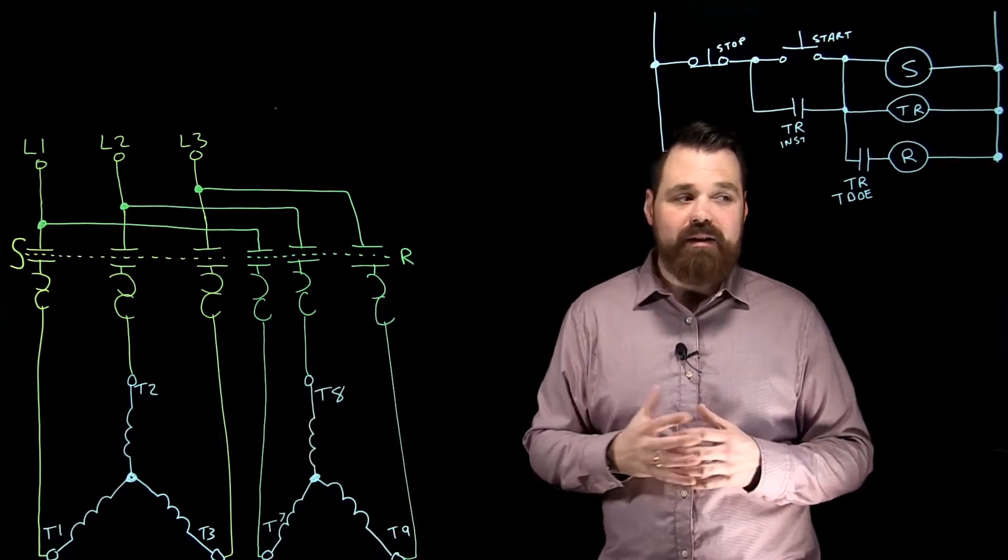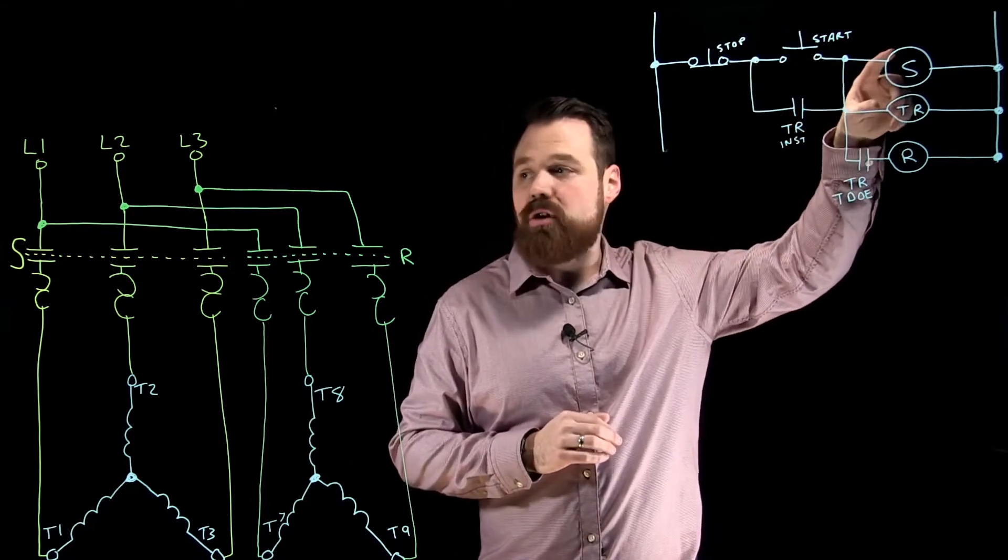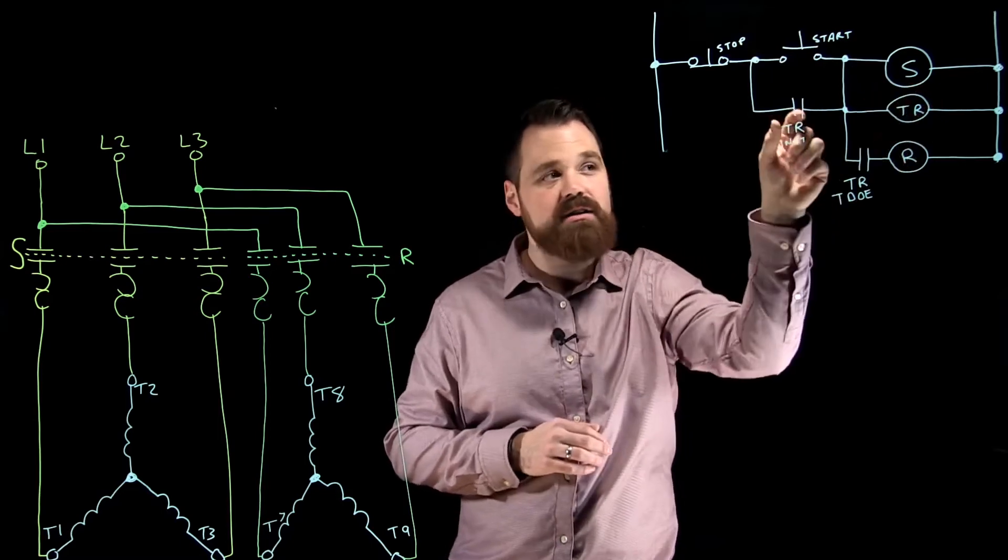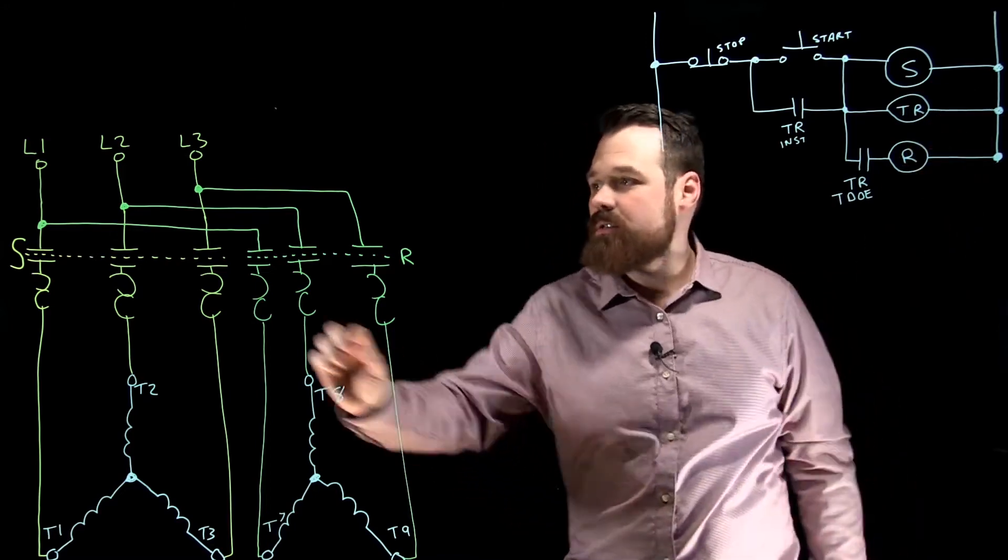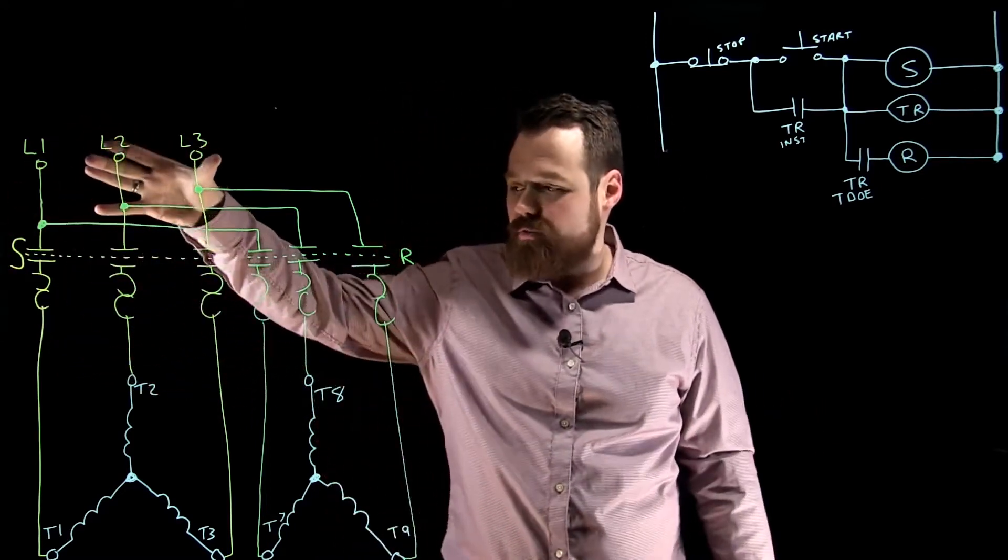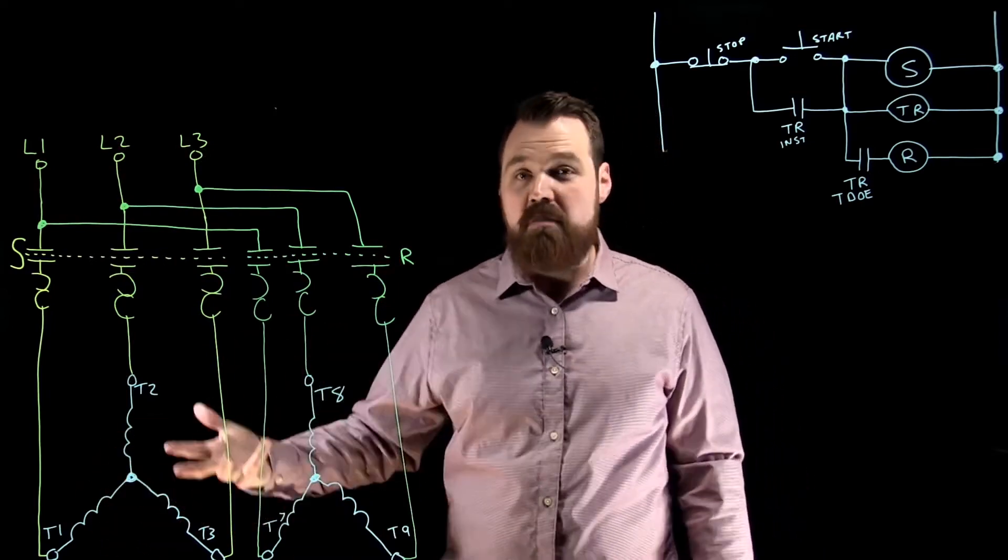So our control schematic looks something like this. Basically we would hit the start button, our start coil would energize as well as our timing relay would energize, closing these instantaneous contacts. When that start coil energizes over here, our starting power contacts energize, current will flow through and energize one of my two sets of windings. The motor will start.